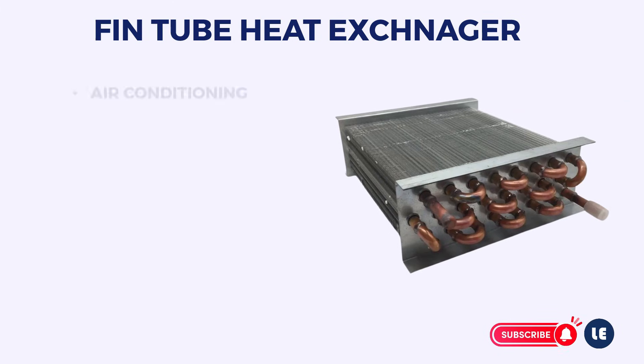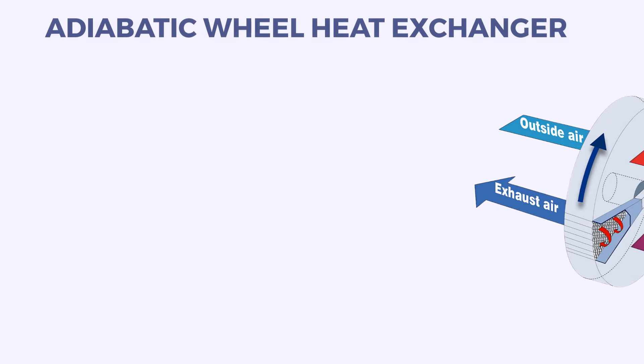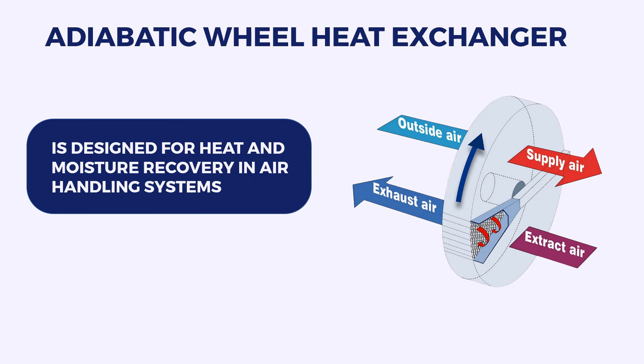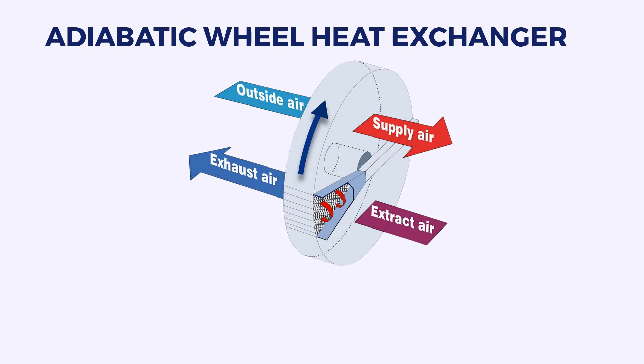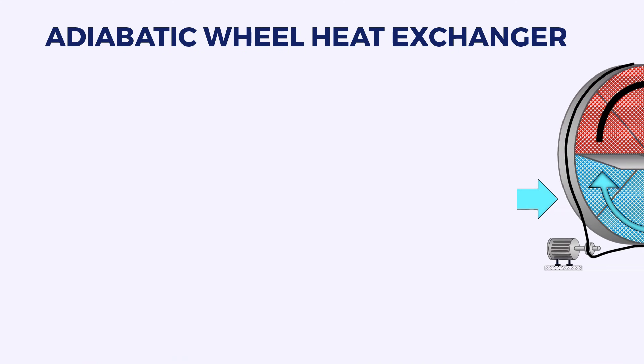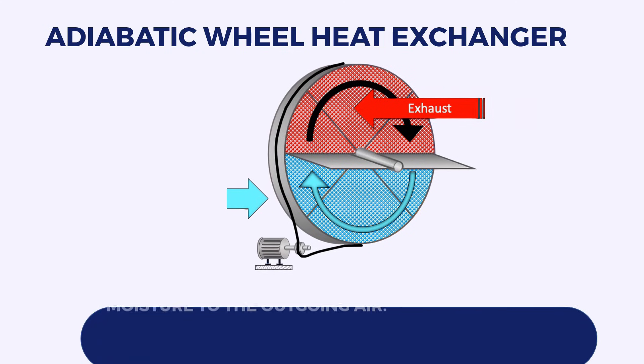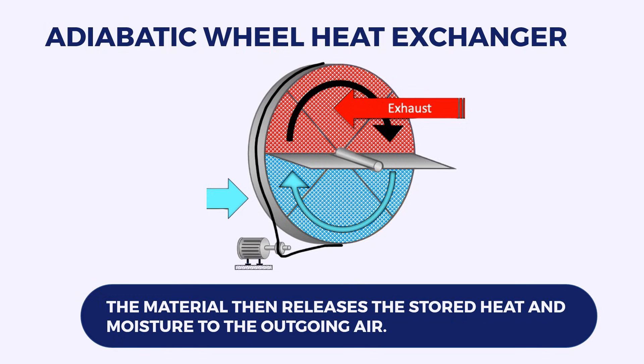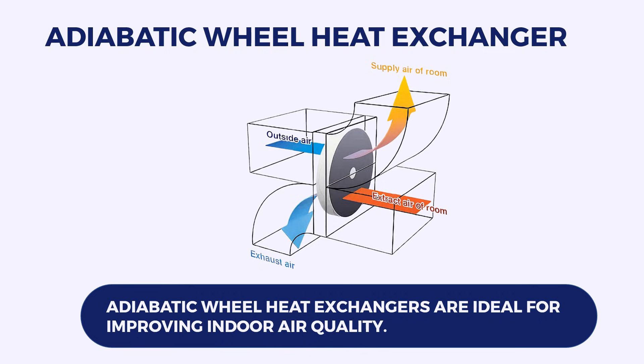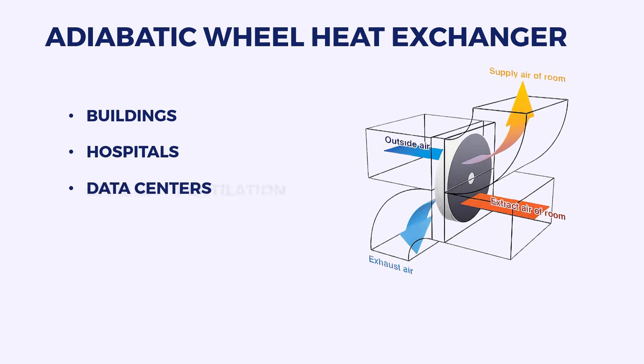Finned tube heat exchangers are used in air conditioning, aerospace, and refrigeration systems. Adiabatic Wheel Heat Exchanger. An adiabatic wheel heat exchanger is designed for heat and moisture recovery in air handling systems. It consists of a rotating wheel with hygroscopic material. As air passes through the wheel, heat and moisture are transferred to the wheel's material, which then releases the stored heat and moisture to the outgoing air. These are ideal for improving indoor air quality and are used in buildings, hospitals, and data centers for energy-efficient ventilation.